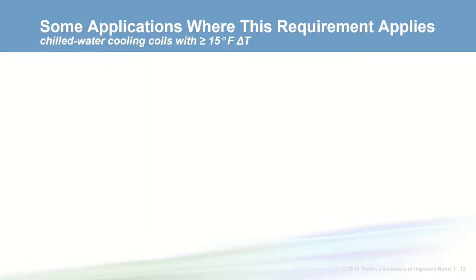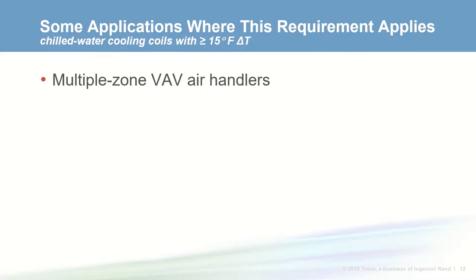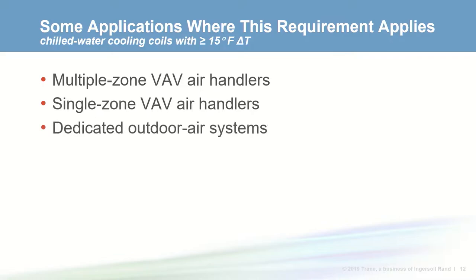So what applications does this requirement apply to? Mixed air multiple zone VAV systems come to mind — they have variable airflow and are usually larger than 5000 CFM. Or a single zone VAV air handler, as might be used in larger zones like auditoriums, gymnasiums, or manufacturing areas. Or a dedicated outdoor air system if it's designed for variable airflow, which would be the case if demand control ventilation is being implemented.